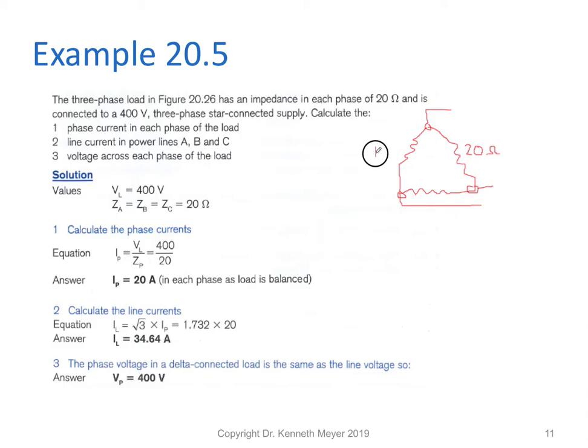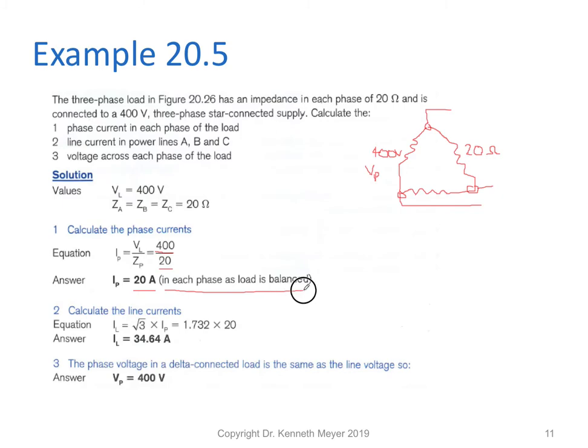To calculate the phase current: we know we have 400 volts across each one, so 400 volts is the phase voltage — it's also the line voltage, but for now it's the phase voltage. Using simple Ohm's Law, volts divided by impedance gives us the current. So 400 volts divided by 20 ohms gives us 20 amps in each phase. Because it's a balanced load — we know it's balanced because each phase is 20 ohms — we can apply this formula directly.